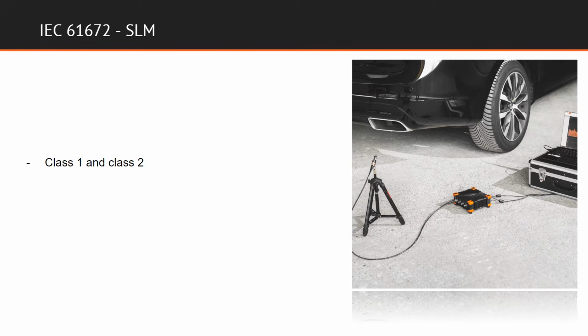Generally speaking, sound level meters are divided into different classes of accuracy, where Class 1 is intended for precision measurements and Class 2 for simple measurements. Approximate accuracy for a sound level meter of Class 1 is 1 dB and 2 dB for Class 2, meaning the accuracy requirements for the SLM to pass the calibration process are different for Class 1 and Class 2.